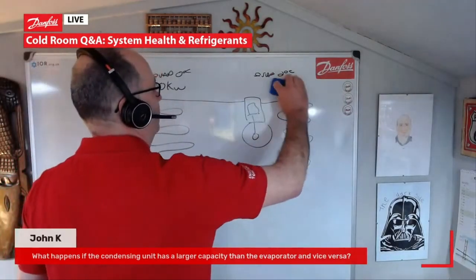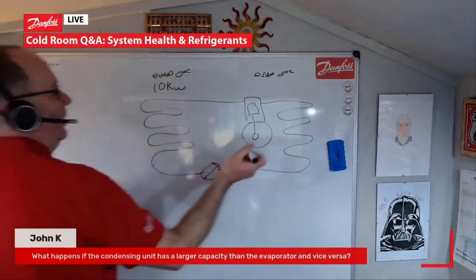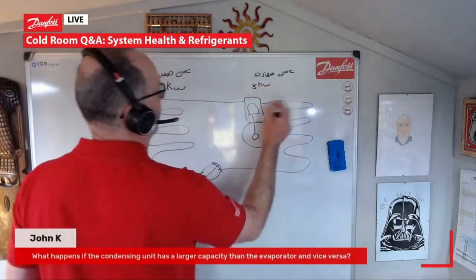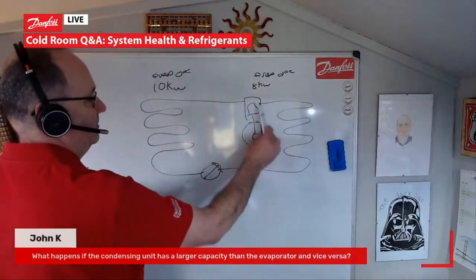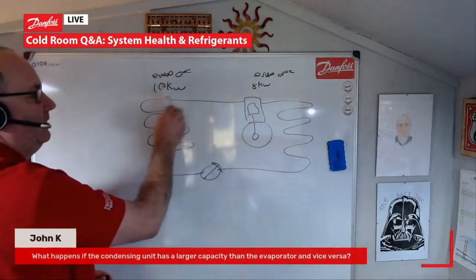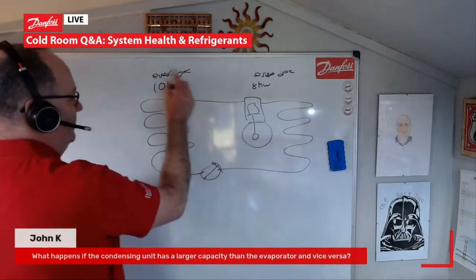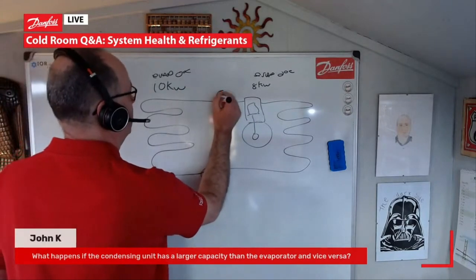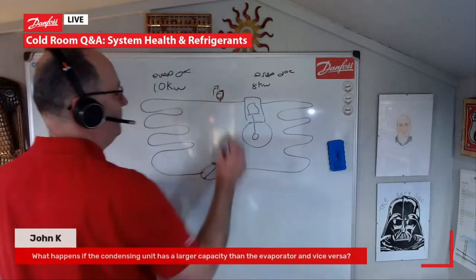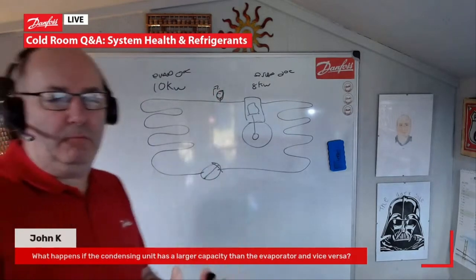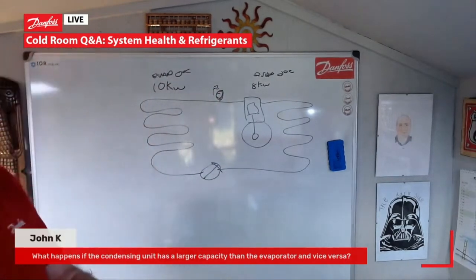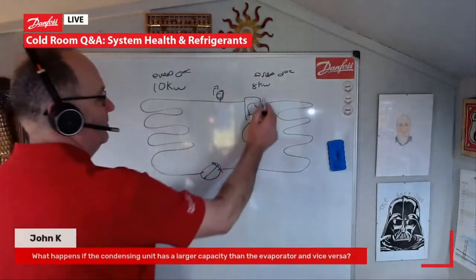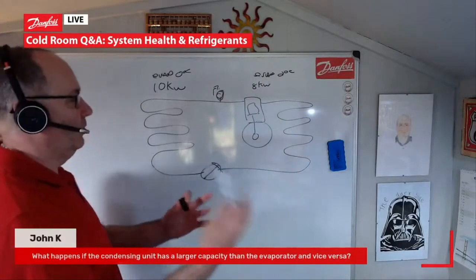If, however, we have — let's say — a 10 kilowatt evaporator and an 8 kilowatt compressor, that compressor is smaller in capacity than the evaporator. What will happen is that because that is a larger evaporator, our suction pressure coming back to our machine will rise — might not rise by much, maybe a few PSI — which in effect is good, because it's giving our compressor something to work at.